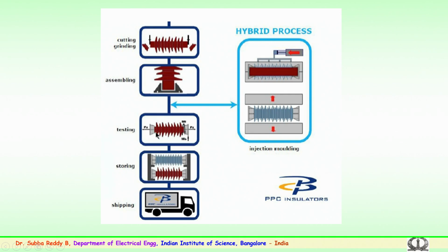finished insulator, the post insulator. Here you can see the metal end fittings on both sides. So, here again the testing, electrical testing and mechanical testing as prescribed by the standards, is being carried out. Once the equipment undergoes certain prescribed standards, which are again routine, acceptance or type testings involving both mechanical and electrical tests as prescribed for a particular voltage level.